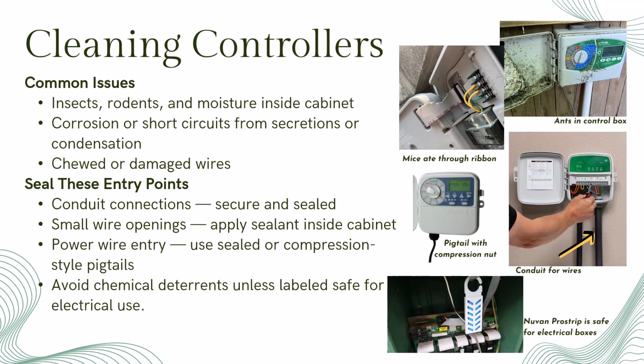Start with the conduit connections. These should be tightly attached with the correct fittings. Then check for small openings around rain sensor or pump relay wires and seal them from the inside of the cabinet. Finally, look at the power wire entry.